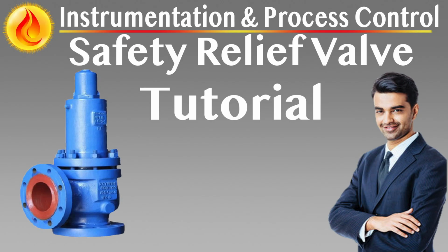Thermal expansion relief valves, TERVs, are used to protect against pressure buildup in blocked-in piping due to thermal expansion. Design standards: standard size 25 mm by 25 mm flange, minimum orifice 0.71 square centimeters. Threaded connections permitted only on bronze valves and only for water service. One-piece body and bonnet is preferred. Screw connections not allowed.